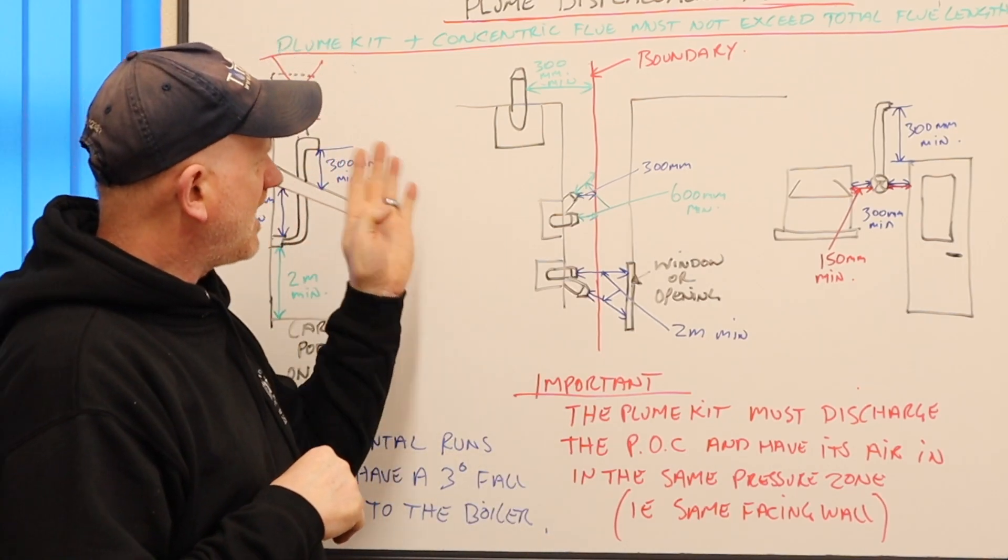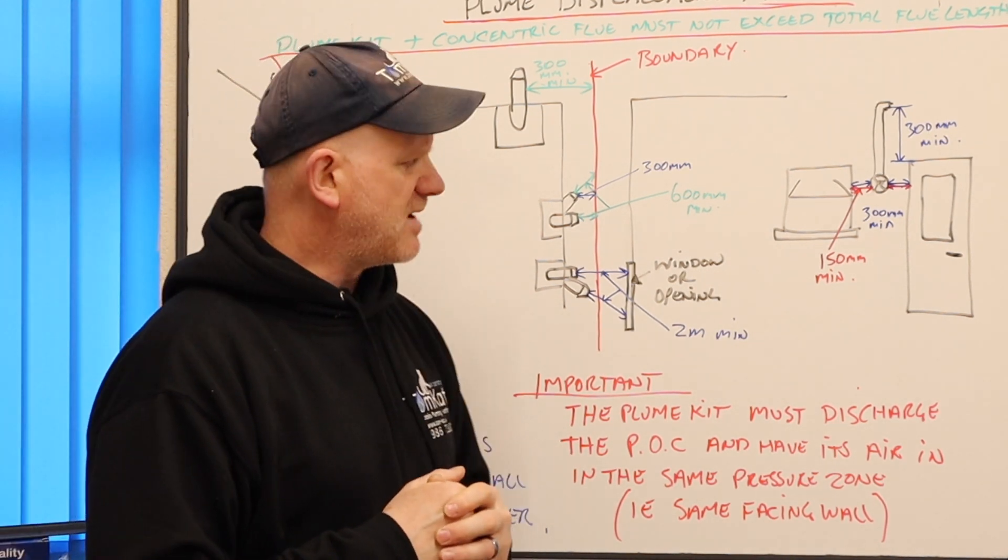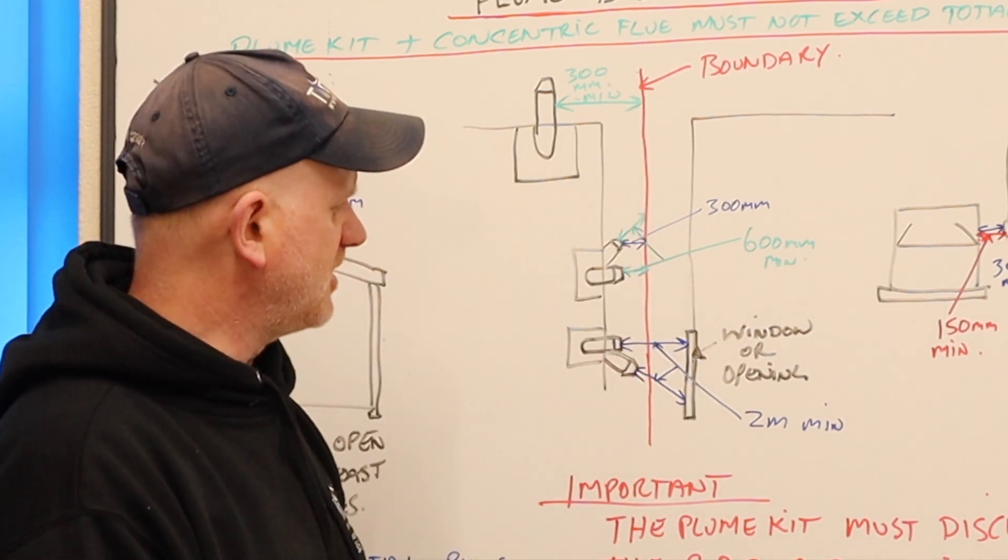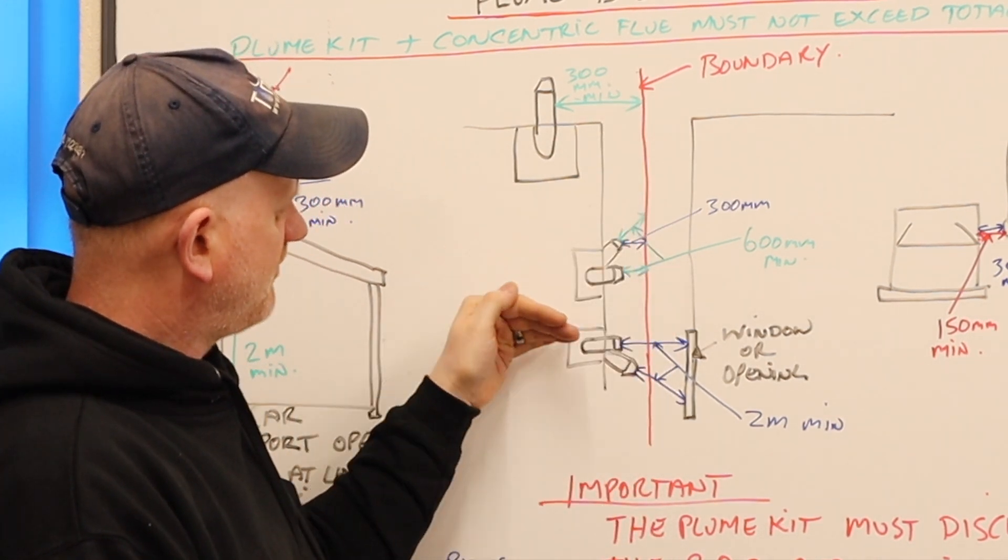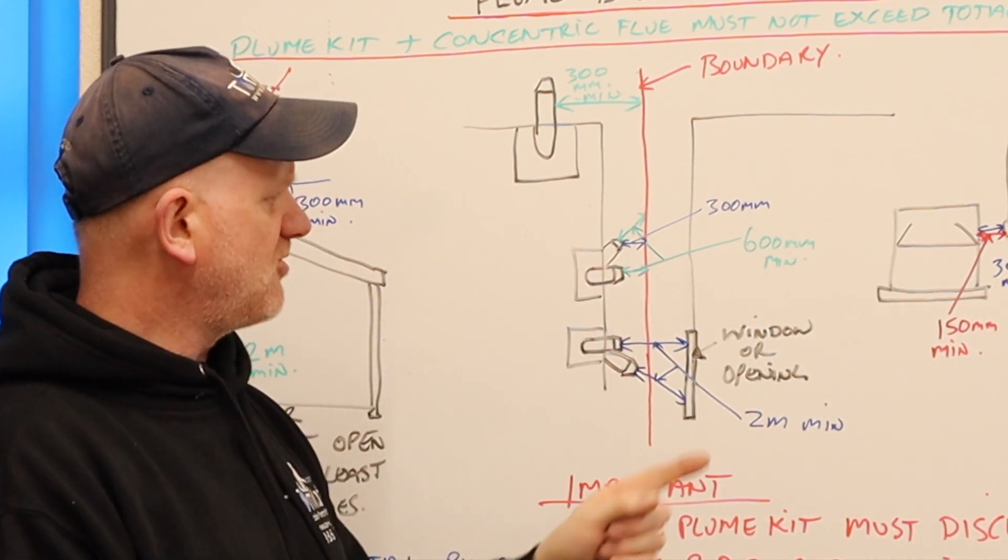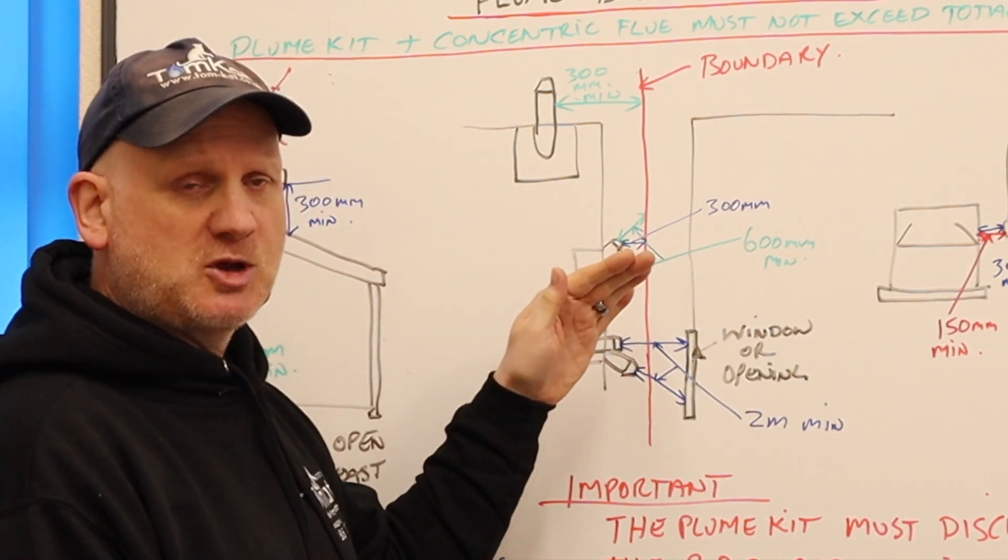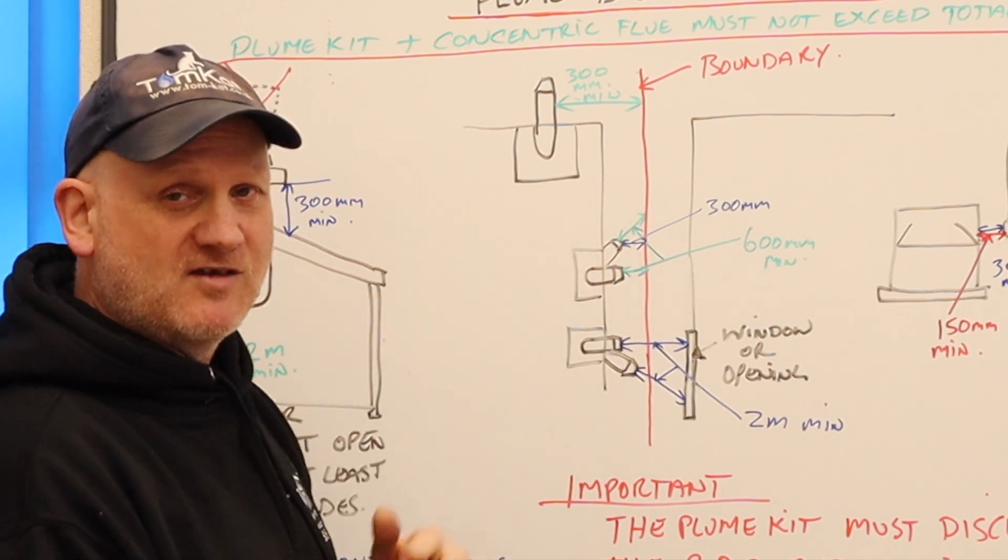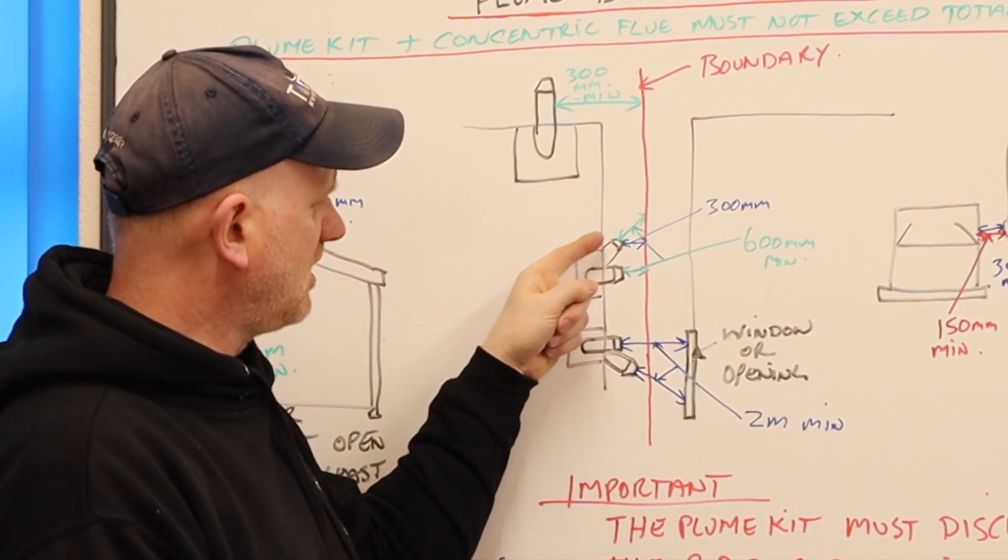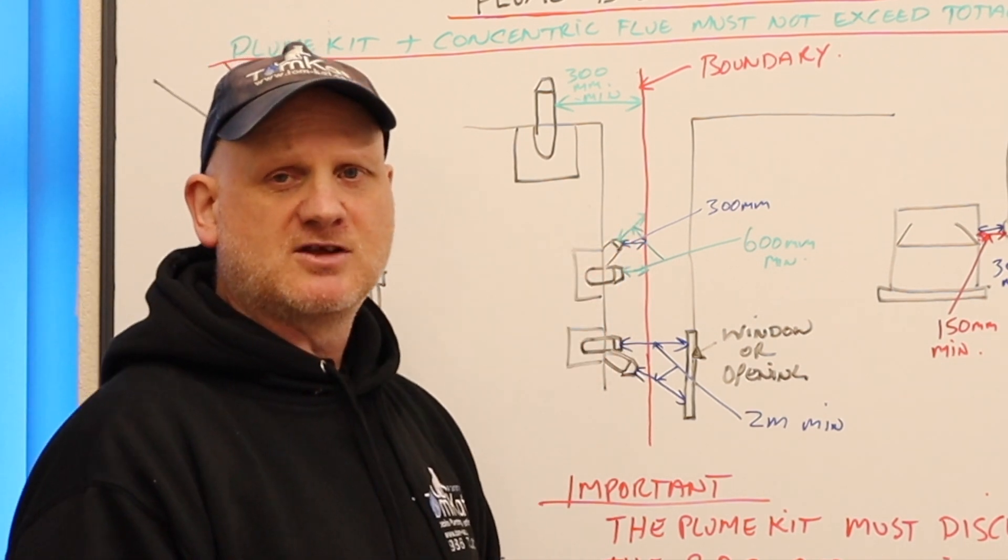Now, one of the other things you'll find is boundaries. How far we need to be away from boundaries. So we've got two houses here split by the middle with a boundary and we've got the flue facing the boundary. So if the flue is facing a boundary it needs to be more than 600 millimetres away. But if we have a plume kit and we turn it to 45 degrees that can be reduced to 300 mil going straight across because it will give you 600 mil on that 45 degrees.